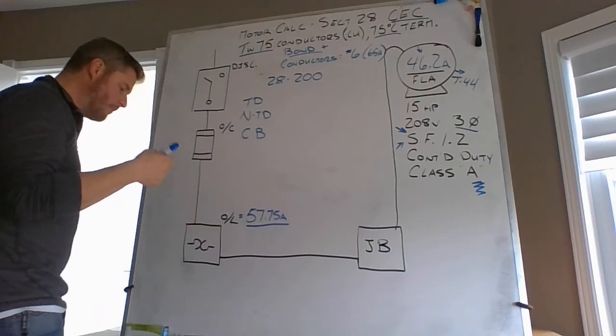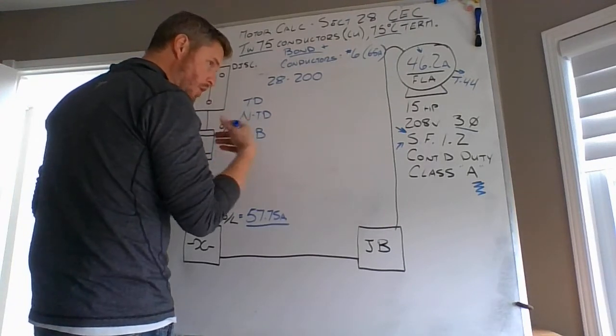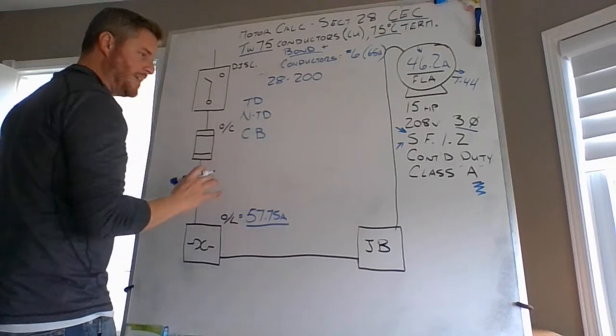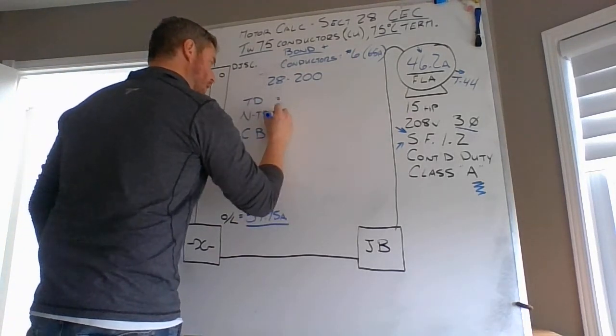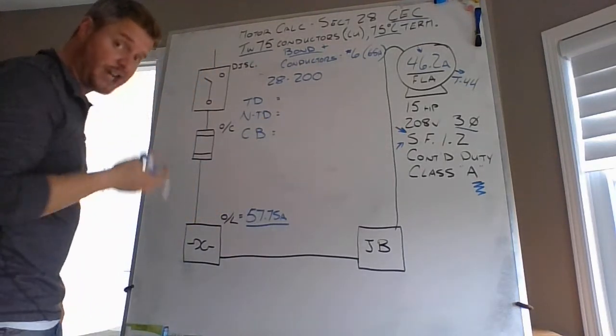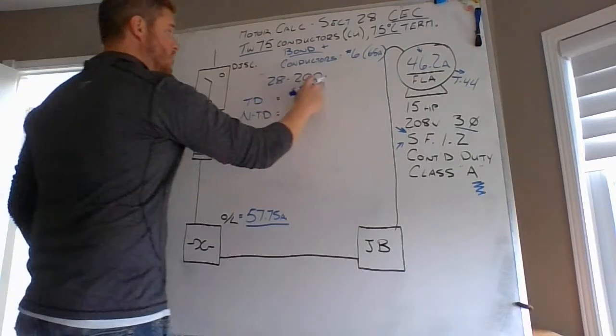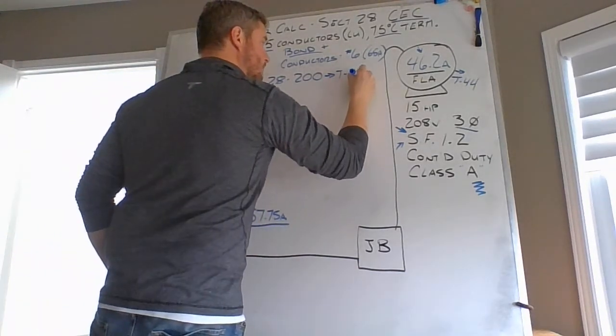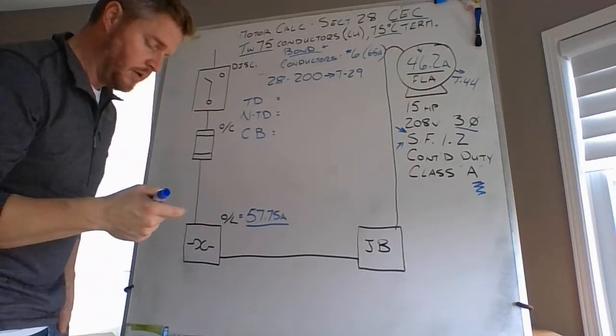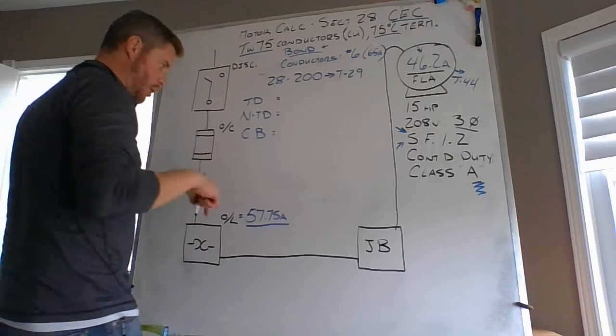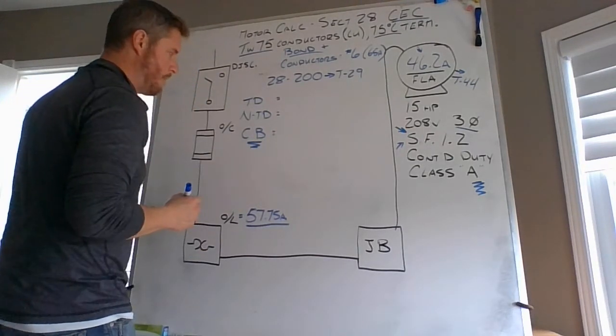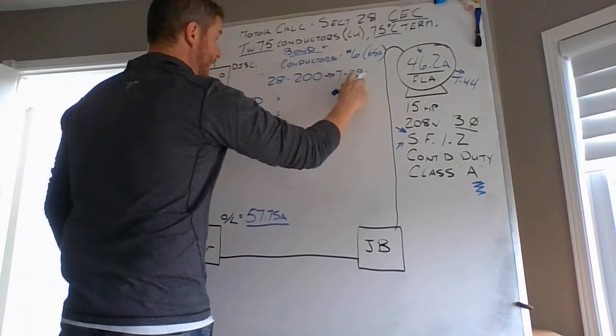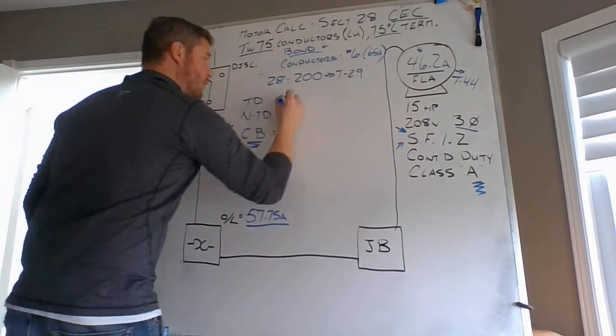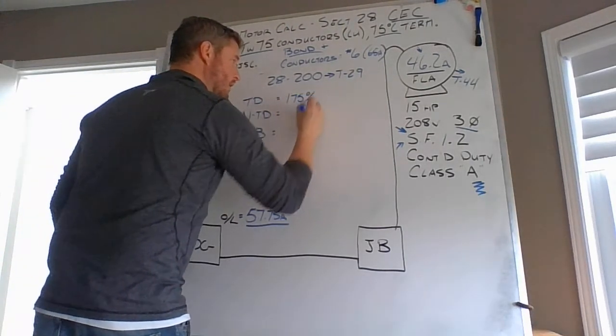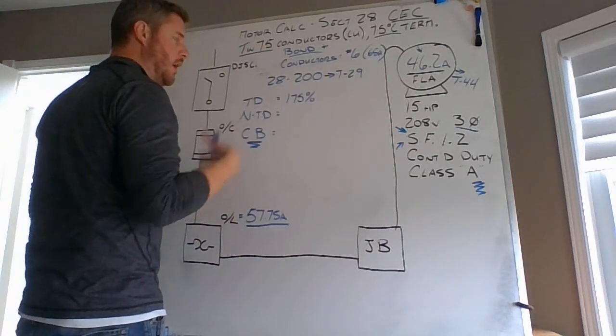Now, I know that excerpt from Motor Control talks about a 10 amp motor and we install a 20 amp overcurrent device. That's not the same case for us with the Canadian Electrical Code Book. I have different values for different types of overcurrent protection. And coming from 28200, it also sends you to table 29. Looking at time delay fuses, non-time delay fuses, and inverse time circuit breakers, or we just call those normal circuit breakers, your multipliers are generated from table 29 in your Canadian Electrical Code Book. And for a time delay fuse, you're looking at 175%.